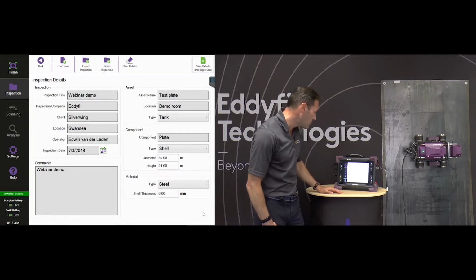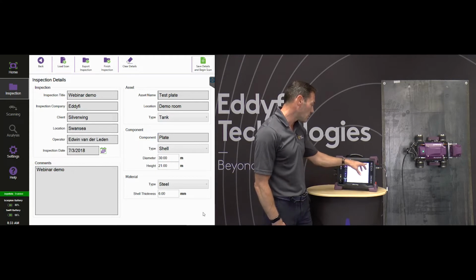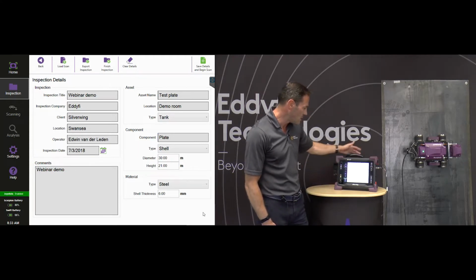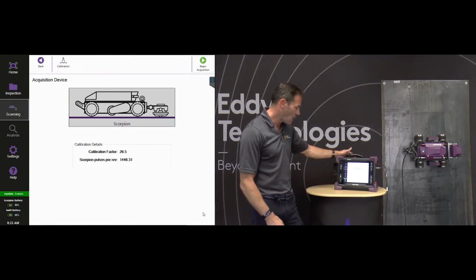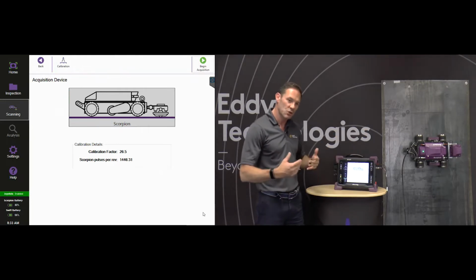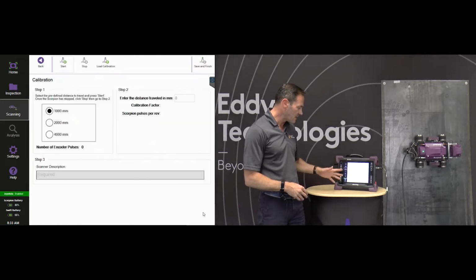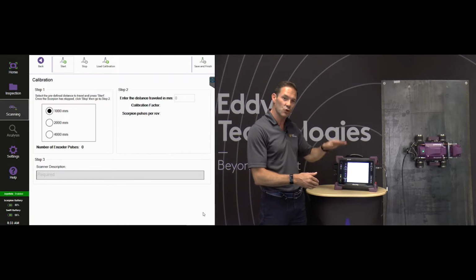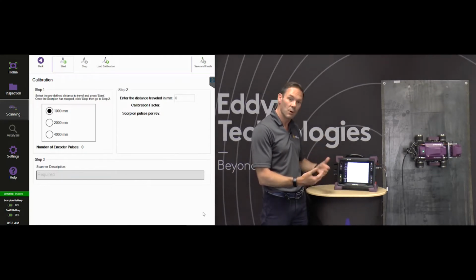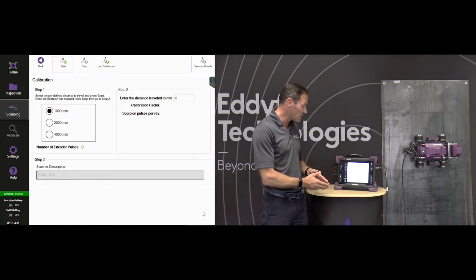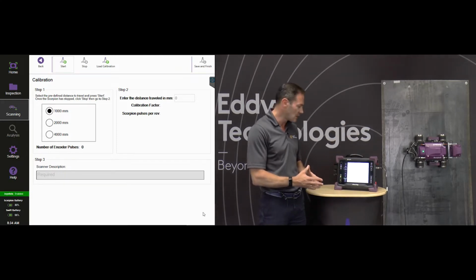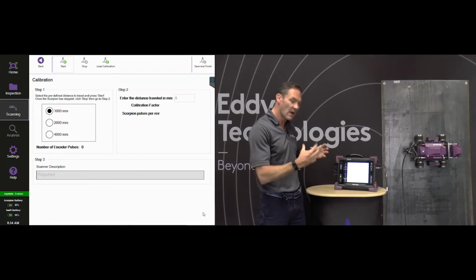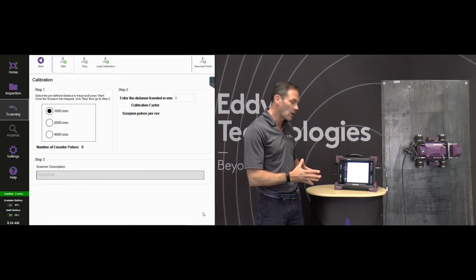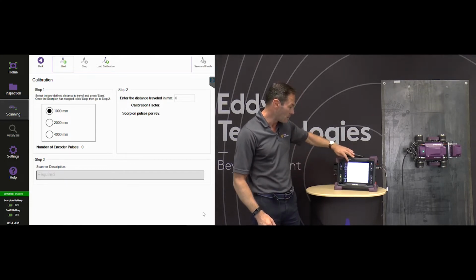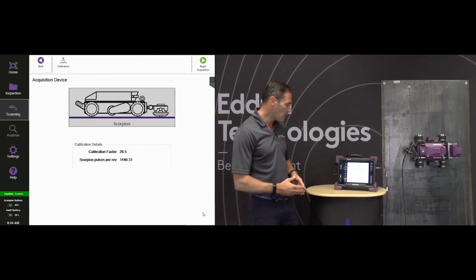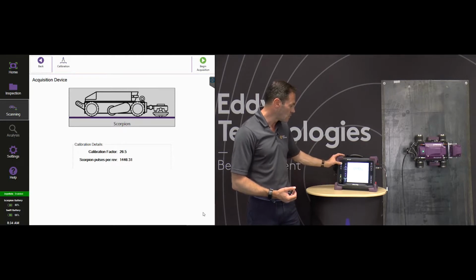Then if you want to continue, you basically go to save details and begin scan, and that will bring you to the data acquisition unit option within the unit. First thing you would want to do is calibrate the unit for the encoders. So there's not the UT calibration, but the encoder calibration. For that, you click the calibration option, and what it basically does, it travels a certain distance, which you can predetermine before you actually do the calibration. So if I set it at 1000 millimeters, the unit will run until it thinks it has 1000 millimeters. Then you can actually measure the real distance that it's traveled, and therefore compensate and calibrate the encoders as such. We won't do it this time, but you can also save that file and reload that file whenever you need to. When I'm ready for my inspection, I actually will turn the unit around.